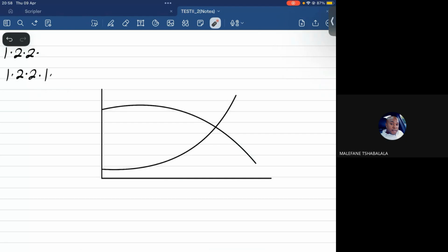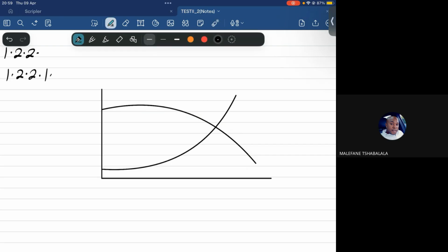Remember, when the two pumps are connected in series, in order for us to get the performance point or the working point, we must multiply the readings of the characteristic curve by 2 in order for us to get the second pump characteristic curve.